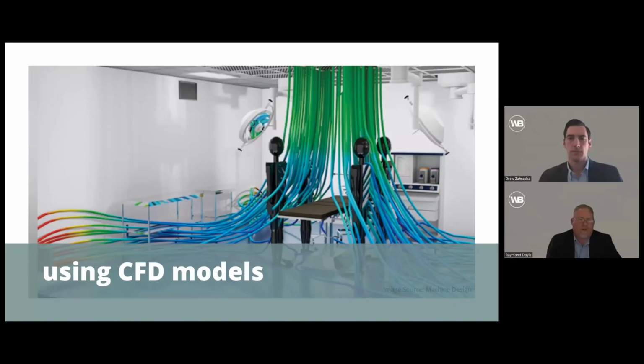So then the next thing we talk about is the design tools, and basically when we're trying to design clean rooms, we use different tools. We talked about different ways to lay out airflows and different HEPA filters in different locations. But the next tool that sometimes is applied is CFD, which is computational fluid dynamics. And it's not applied everywhere and sometimes misapplied. But in this particular image, you can see how it's important to understand that the HEPA filtered air blows straight down over a table, and that creates the cleanest environment in the space.